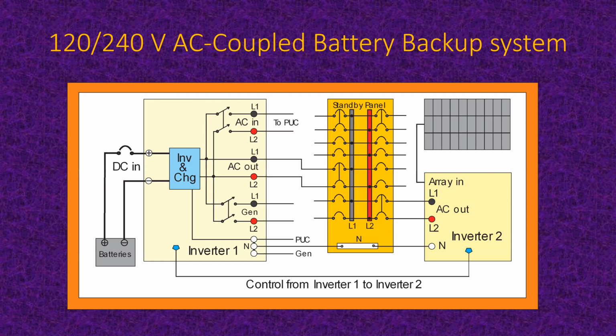Here's another question. Let's look at that right away. If the PV array is on a pool house about 120 feet from the house, what equipment goes into the pool house and what equipment goes into the main house? It partly depends on what's already in the pool house. We've had a couple of situations like this recently come up in our designs where they put a fair amount of PV on the roof of the garage. So if your pool house roof is a nice south-facing unshaded roof, you might put some of the solar on the roof of that house. Depending on your connection to the utility, if you can backfeed a circuit breaker to tie into the utility, and actually, even if you don't have to do that, if you have to do a line side tap or some other way of getting to the utility, it turns out that actually you can put some of it on the pool house and some of it on the main house.